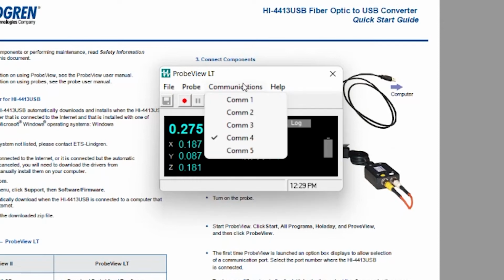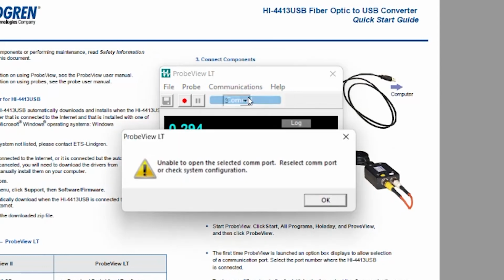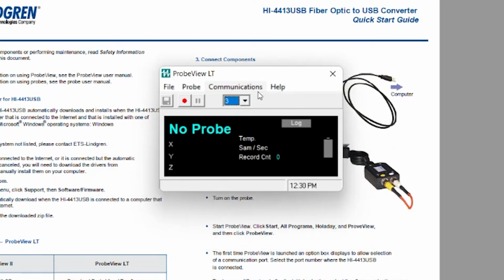Now this is particularly important as this is the communications port that your ETS Lindgren HI-6006 field probe is connected to. So we have ours connected to port 4 on our PC. However, should you have it connected to a different port, you want to be sure that is selected. So if you do select a port that the probe isn't connected to, you will receive an error, just like that. We have ours connected to port 4 or communication 4, and you will see we are getting field readings now. So when you are going through the ProbeView software, the quick start guide and the user manual are great locations to find answers to a lot of the common questions. Otherwise, you can always reach out to ETS Lindgren as well.